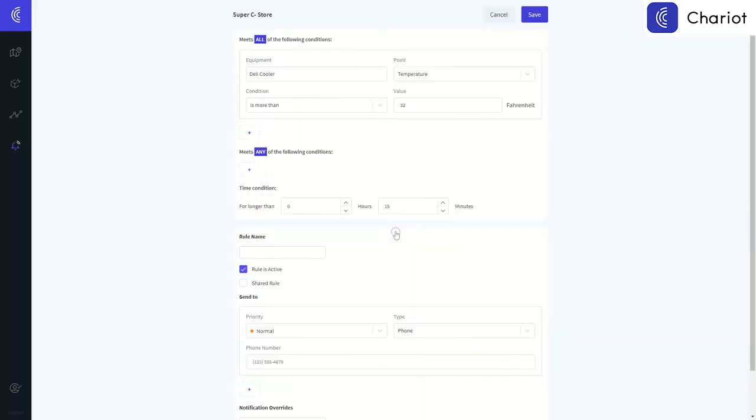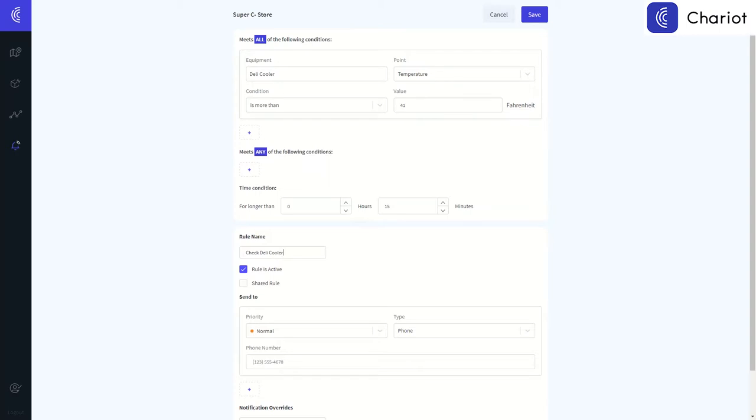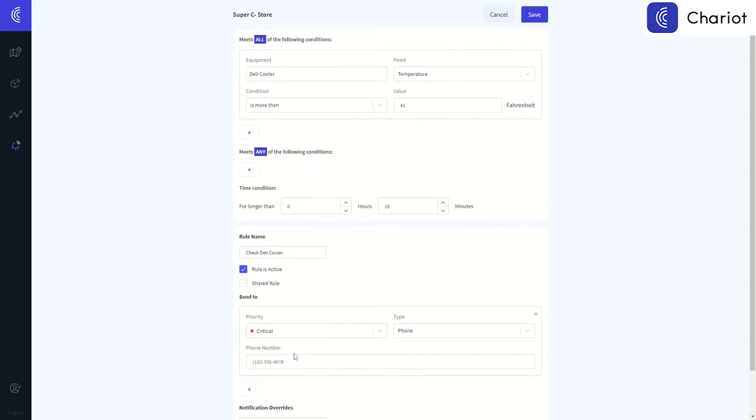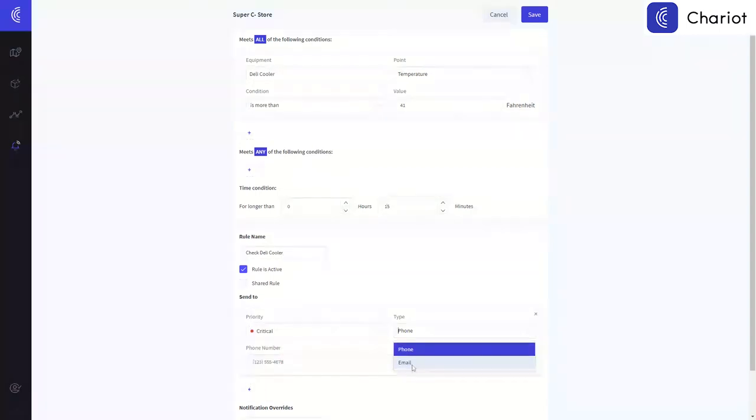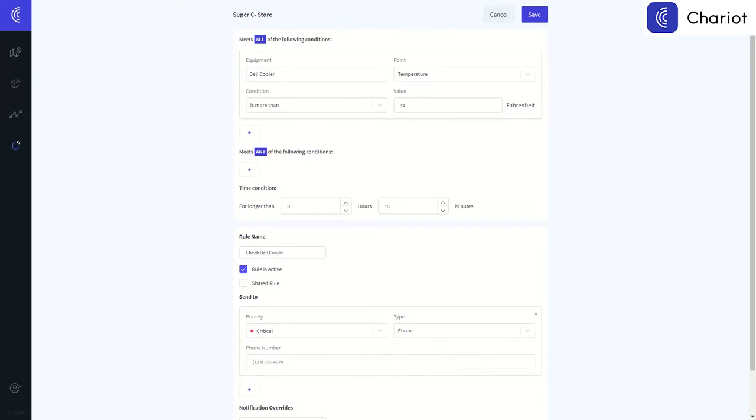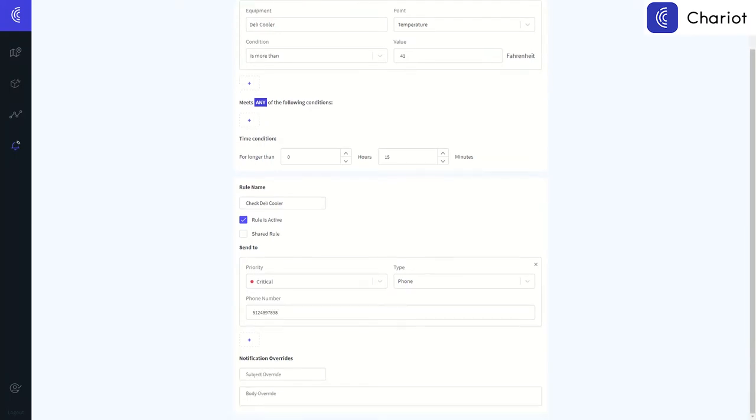In this case, deli cooler. And we're going to say, if this thing's warmer than 41 degrees for more than 15 minutes, then we're going to send a notification. In this case, we'll mark it critical. Do it by phone, so it will send a text to the prescribed number. And either use default notification text or custom notification text, whichever works best for your workflow processes.